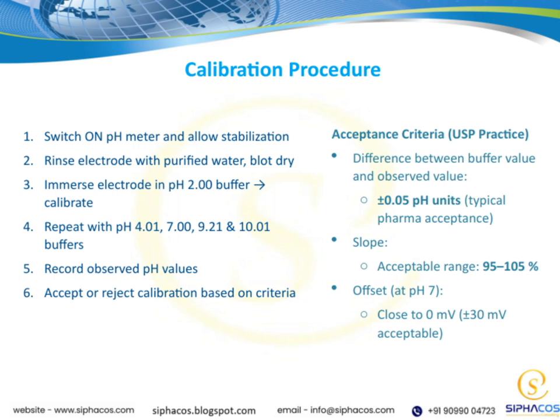Then, there's the offset at pH 7, which should be close to 0 millivolts. Generally, an offset within plus or minus 30 millivolts is acceptable, ensuring our electrode isn't drifting significantly from the true value. Now, for the calibration procedure, we start by switching on the pH meter and allowing it to stabilize, which is key for accurate readings.